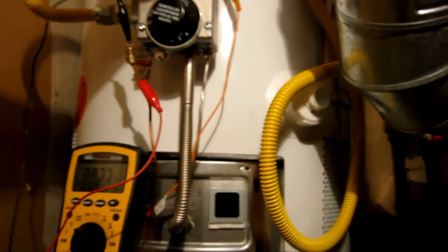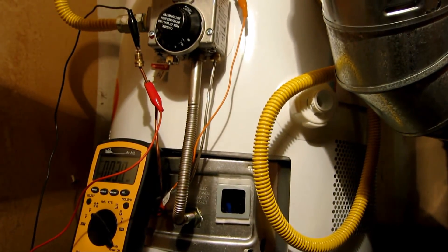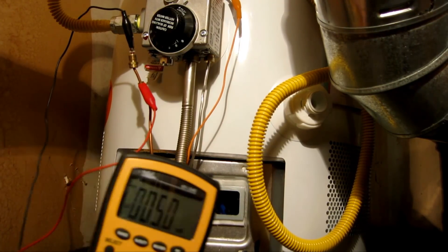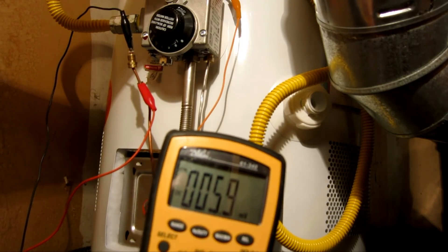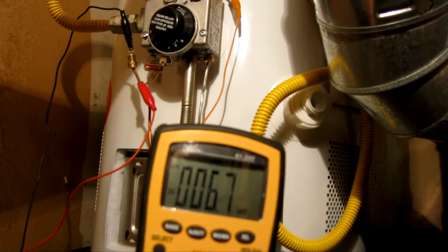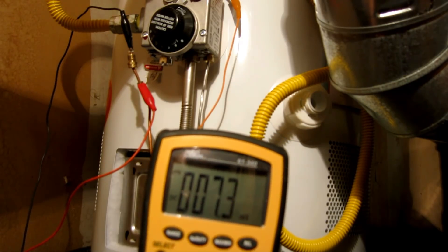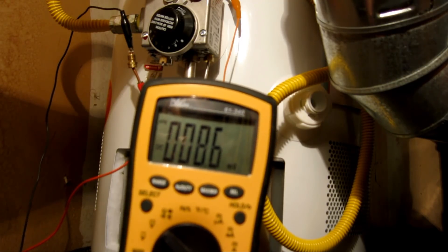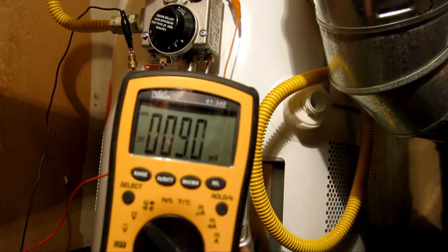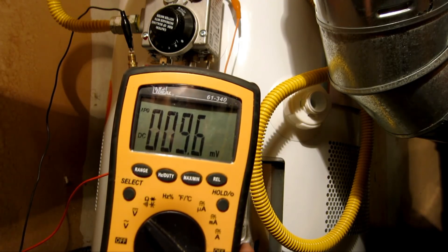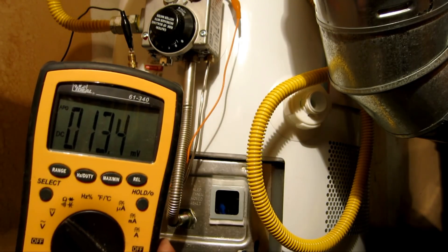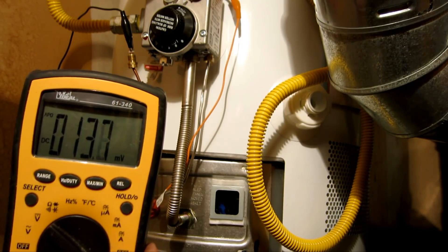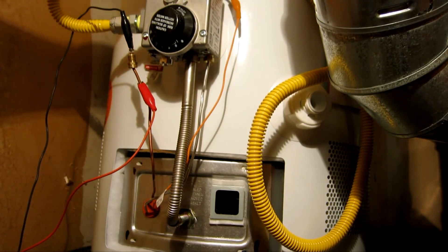Okay, I'm going to reattach this. So, the pilot light is on, you can barely see it because I turned on the light. Oh, look, it's increasing, six, seven, it's increasing really fast too. So that was it, that was the problem. The thermocoupler got bumped down. I just had to push it up a little bit so the tip aligned with the pilot. Obviously the voltage, the millivolt is climbing, so this is a good thermocoupler. I'm just going to turn this off.